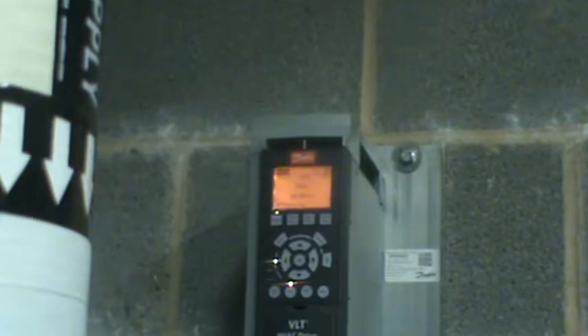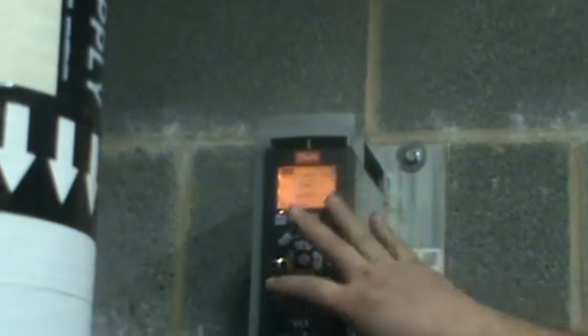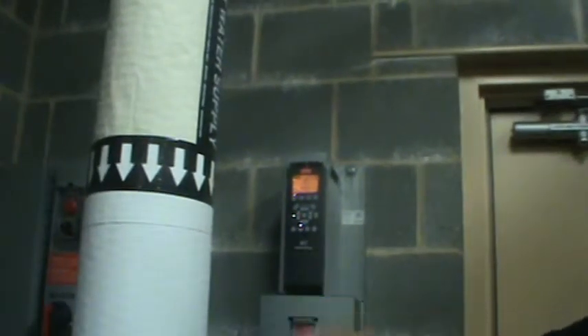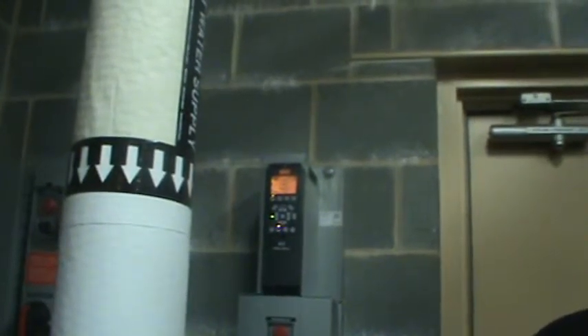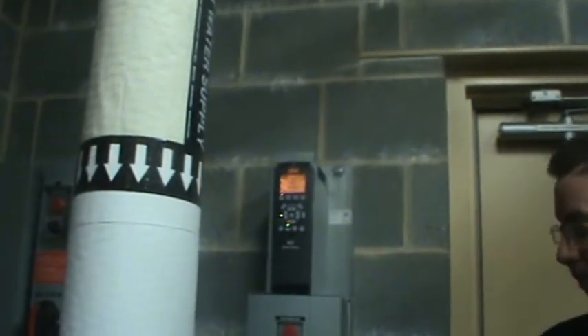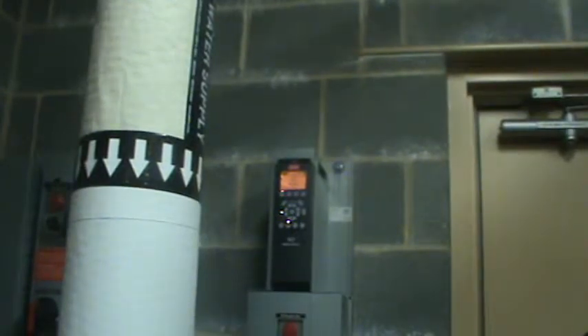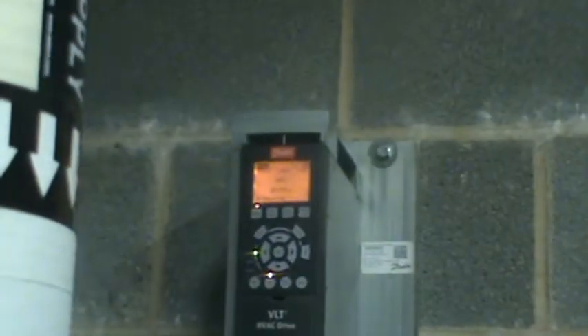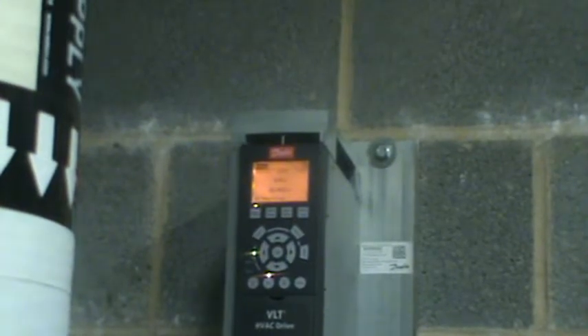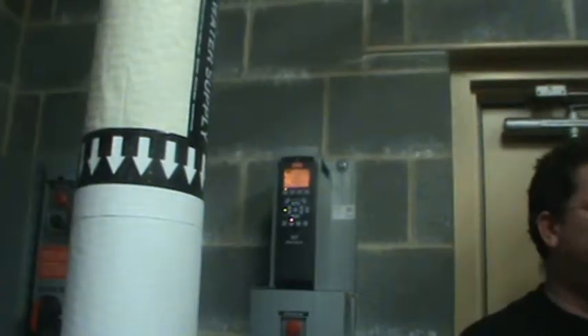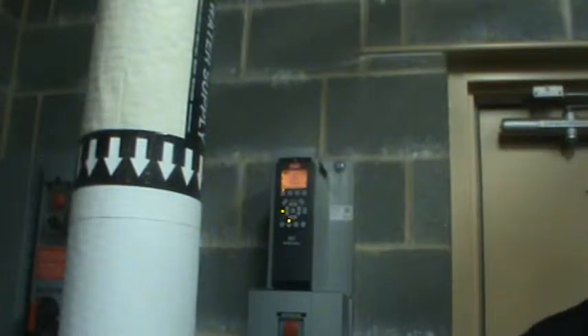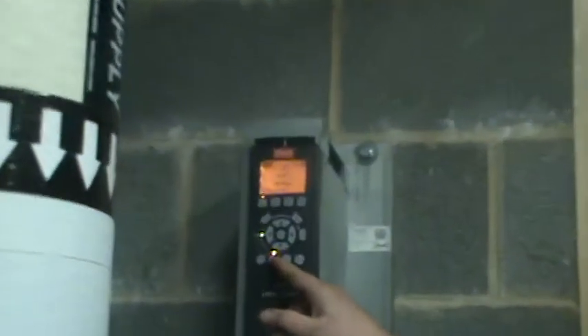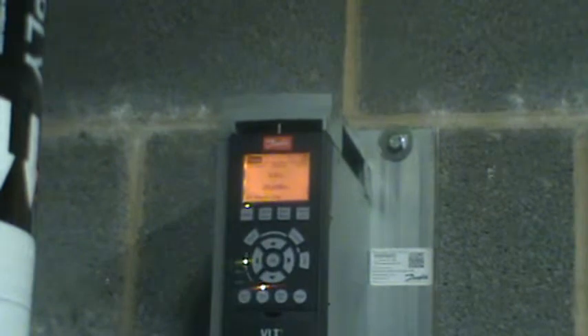Okay. Your main disconnect, your selector switch, and then your actual drive and your keypad and stuff. For the most part, from here down, you guys aren't going to be doing much, unless you have to turn it off for maintenance. Your selector is drive off, auto, and test. Or drive off, bypass, and test. My apologies. It's going to be on, and it's going to be in drive 100% of the time. Okay. Up here, you're going to have either off or auto. Off is just dead stop. It's going to be sitting there waiting for you to turn it back on again. Auto, it will be running, responding to the pressure transducer using the program that we put into it today.